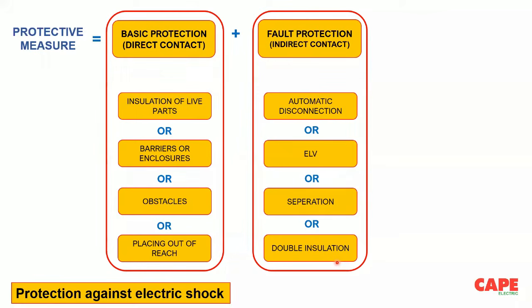In solar PV, especially on the DC side, protective devices for quick, automatic disconnection are not available. For example, fuses are not efficient enough to quickly disconnect. MCBs are not efficient enough to quickly disconnect the supply in case of a fault. There is no ELCB or RCDs available. They are still under development. There is no arc fault detection device, AFDD, for pure DC application. So basically, disconnecting the supply during a fault is very difficult.